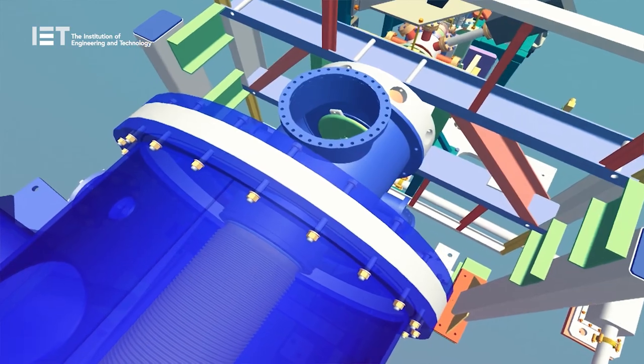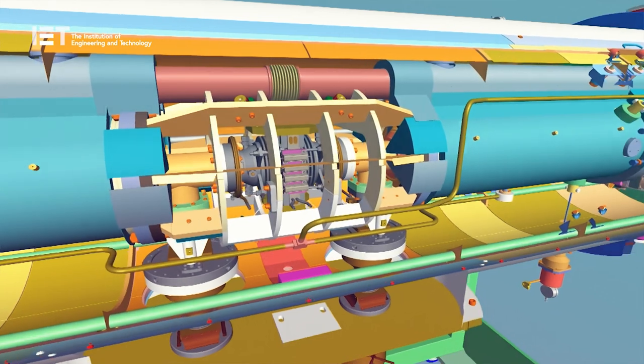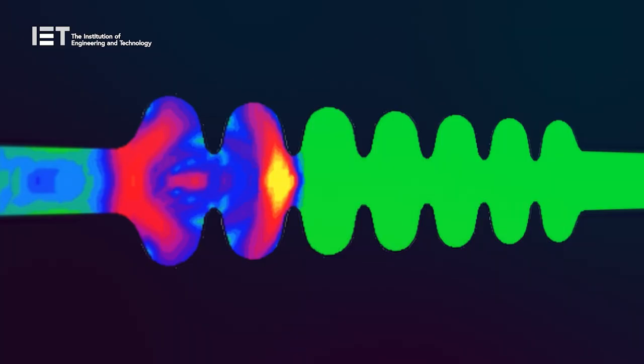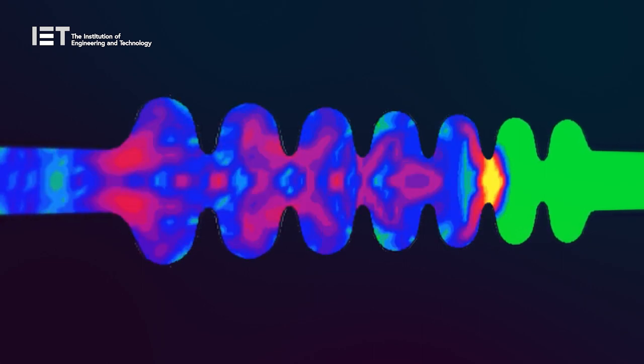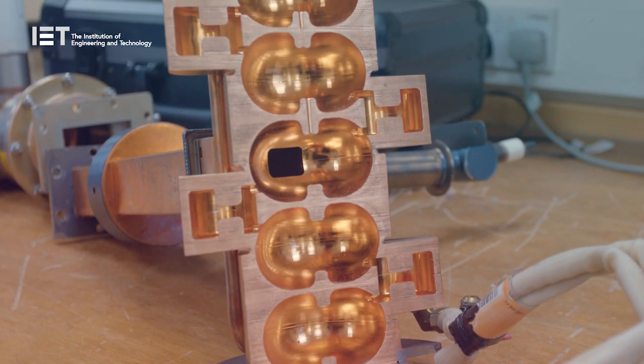Our linear accelerator is comprised of three main parts: an electron gun to produce the electrons, an accelerating cavity, and microwave RF source to produce the microwaves for acceleration. The electron beam interacts with the microwaves to accelerate along the cavity, and then it can be bent by a dipole to create an x-ray source.